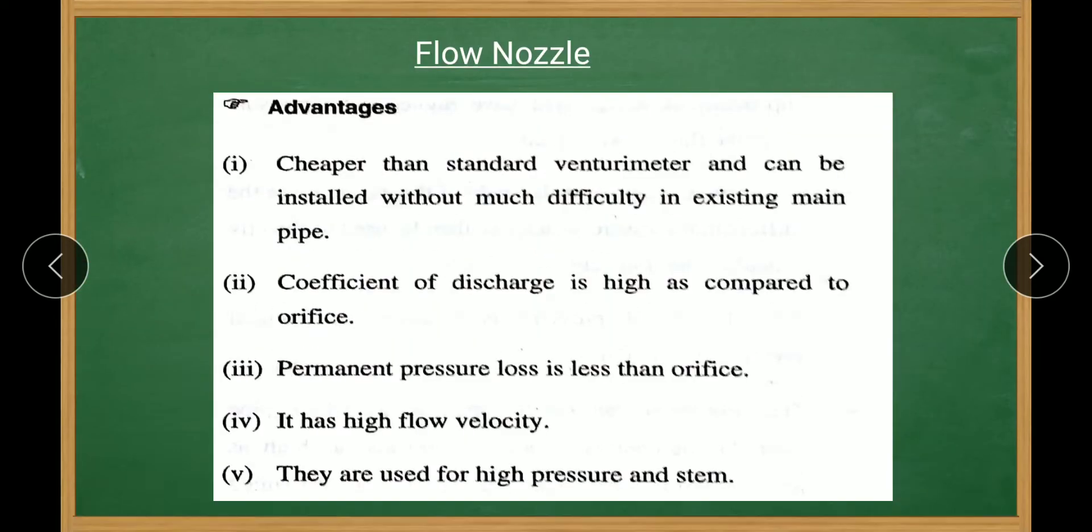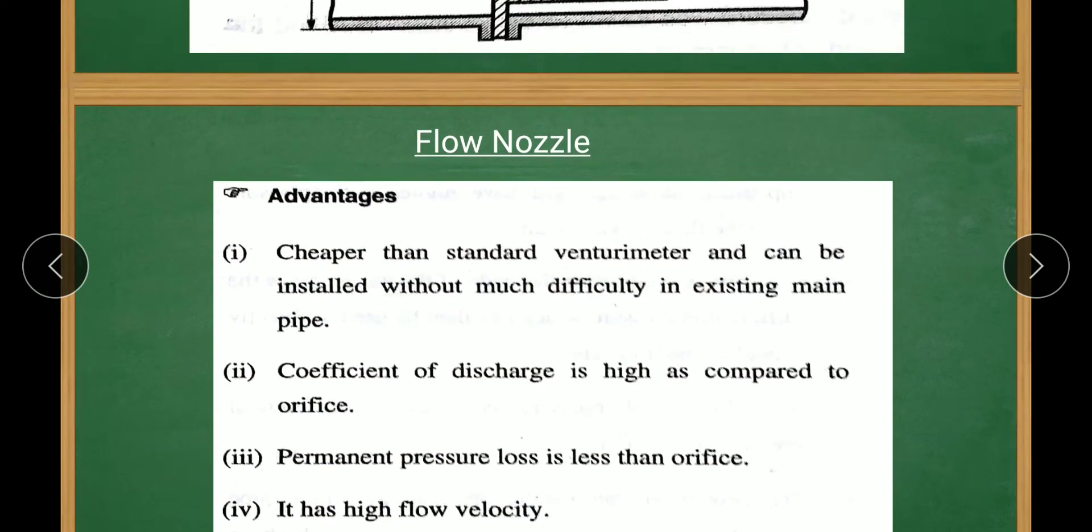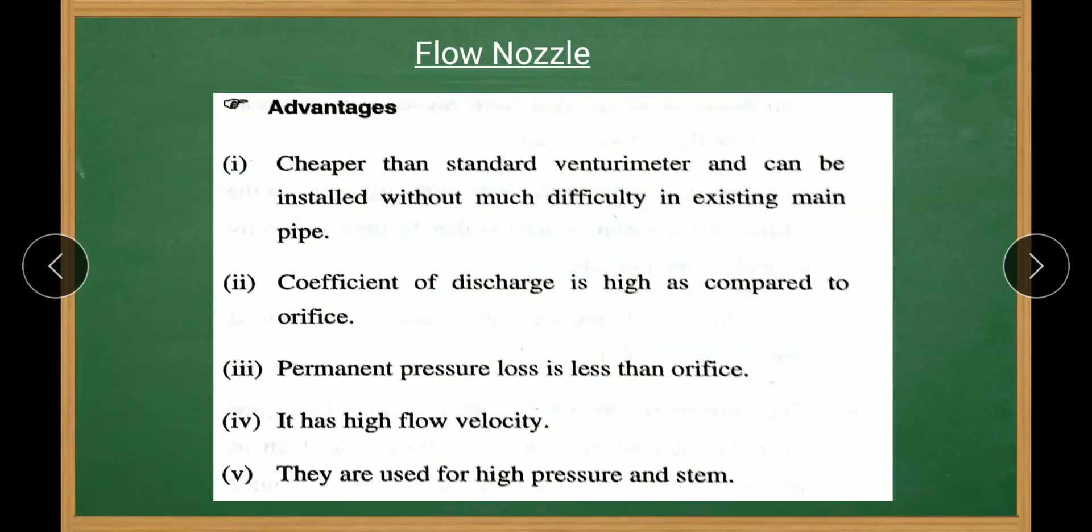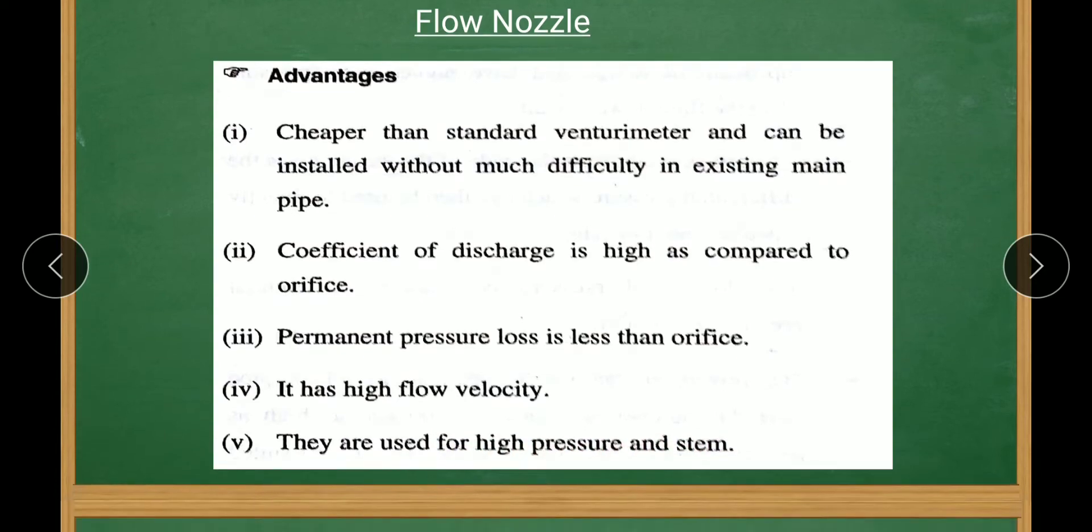The flow nozzle measures pressure difference from inlet and outlet. Advantages: it is cheaper than standard venturimeter and can be installed without much difficulty in existing main pipe. Coefficient of discharge is high as compared to orifice. Permanent pressure loss is less. It has high flow velocity. They are used for high pressure and steam.